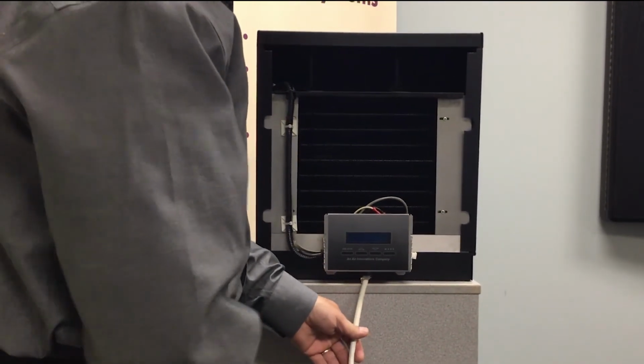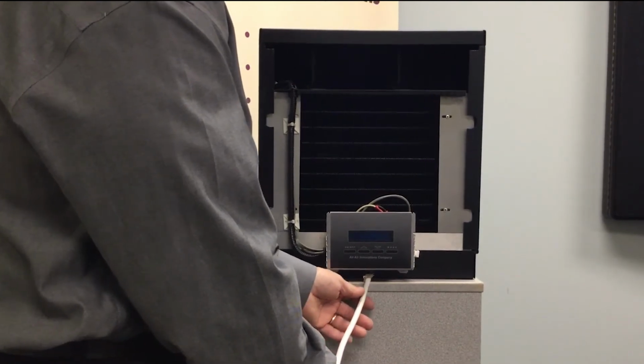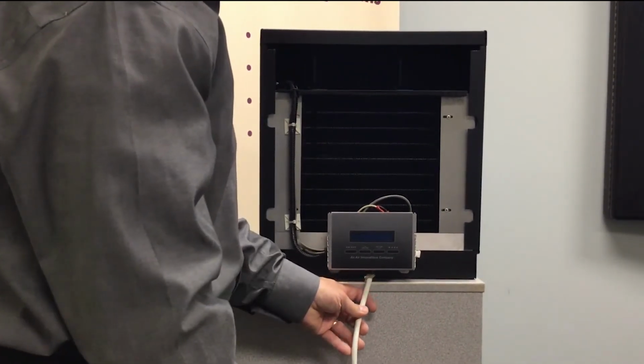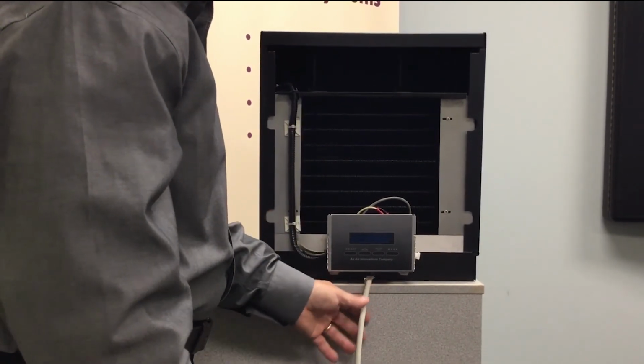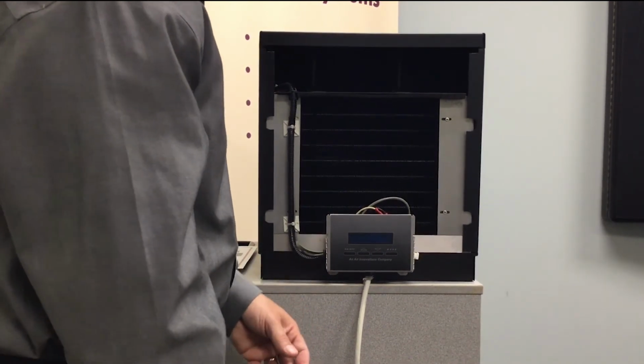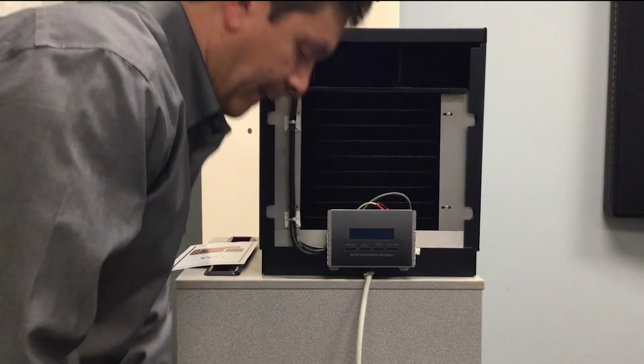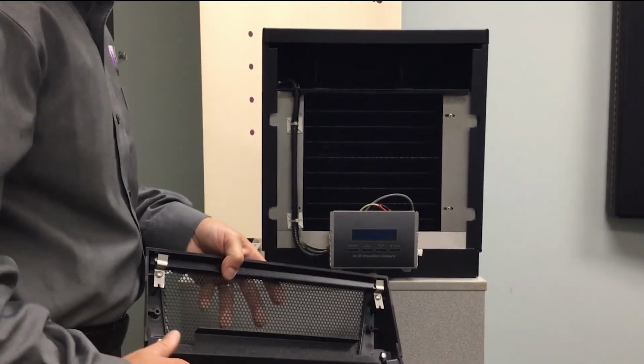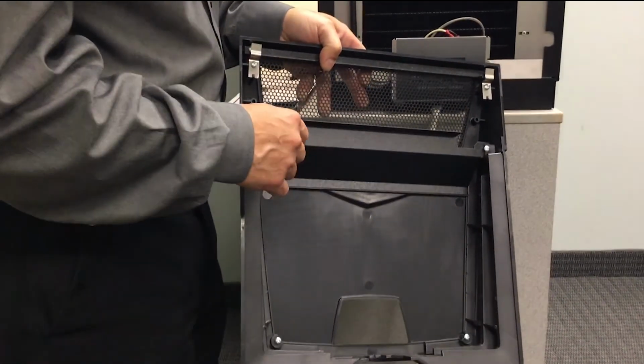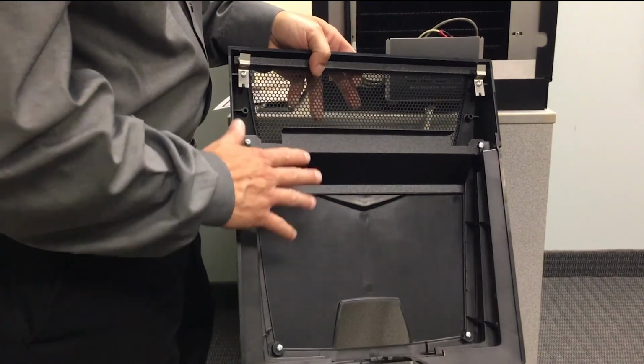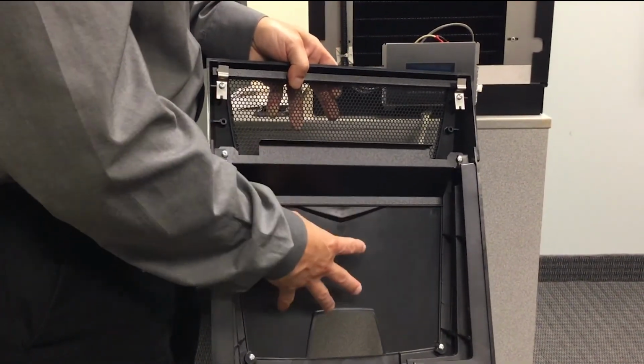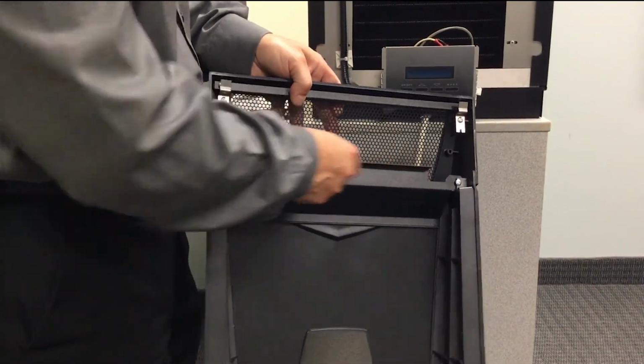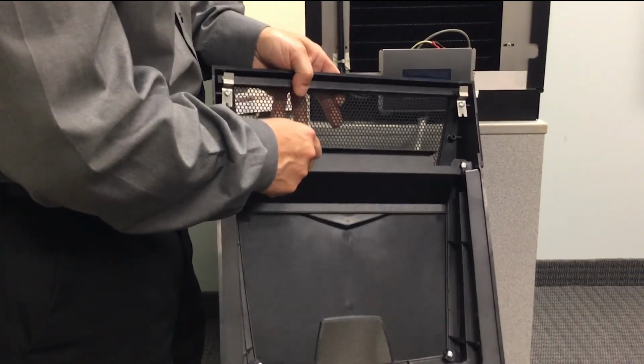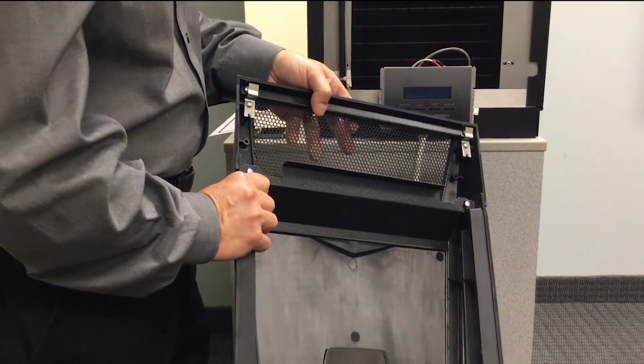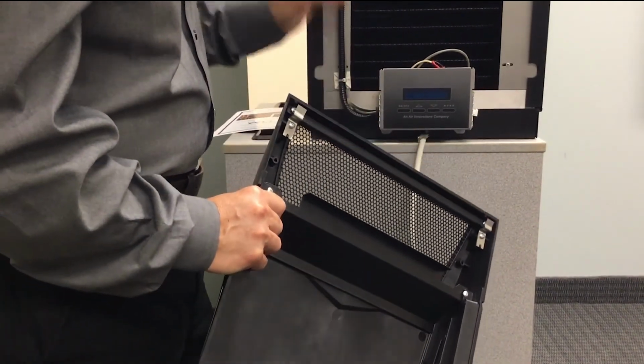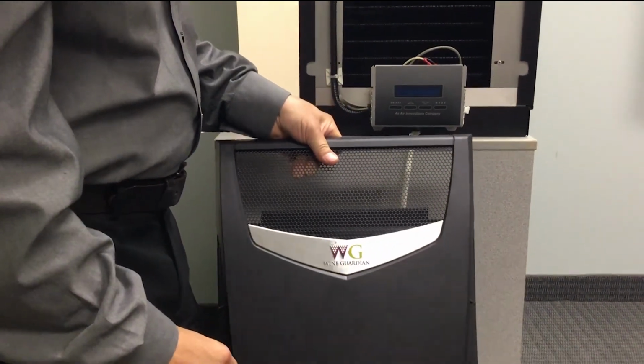This particular unit, we've moved the power cord to the front of the unit. This is for this particular case. It normally ships on the condenser end, and it's a very simple changeover that's pointed out in our operations manual. One thing to also point out, looking at the back of this grill, I don't know if you can see this okay, is the way that this grill is designed, it provides a separation between the return air and the supply air. There's this divider piece here as part of this grill assembly. It's imperative that you're using our grill assemblies and you don't remove them when you're doing an install. The unit will not operate correctly without this faceplate installed.